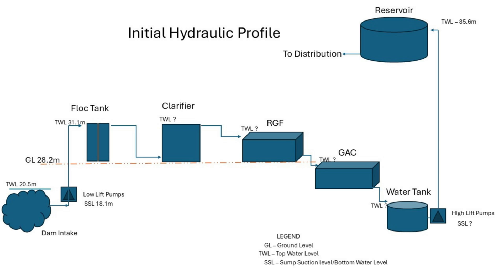Clarified water flows from the top of the clarifier by gravity to the rapid gravity filters — there is a deliberate difference in top water level between the two to allow gravity flow. From the rapid gravity filters, water is collected at the bottom and flows by gravity to the GAC filters. The top water level of the GAC should be at the same level as, or slightly lower than, the outlet of the RGF so that water can also flow by gravity.